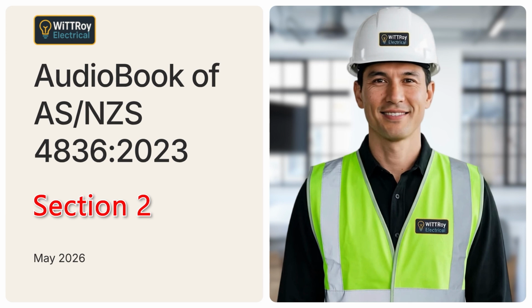Clause 2.3.3 Electric shock. Clause 2.3.3 explains that possible sources of electric shock must be identified before work starts. Electric shock can come from many sources. It can come from voltage between active conductors, between active and neutral, or between active and earth. It can also come from voltage across open switch contacts, undischarged capacitors, disconnected conductors, static electricity, induced voltage, transformer secondary terminals, different earthing systems, incorrect wiring, faulty equipment, and other sources of supply. Other sources of supply may include illegal connections, UPS systems, motor generators, inverters, solar panels, batteries, and wind generators.